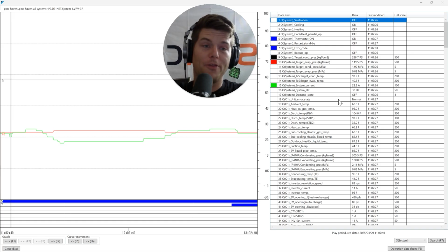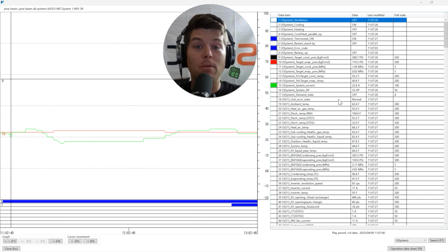So when we're out there in the real world, and this happens almost on a daily basis, you get into these situations and scenarios where you see the problem with your own eyes. It's right there. There's the problem. You're the problem. Just kidding. You're not the problem. Well, maybe you are. The problem is this: low discharge superheat and low suction superheat. Now, the issue becomes, where the hell is it coming from and how do we find it?